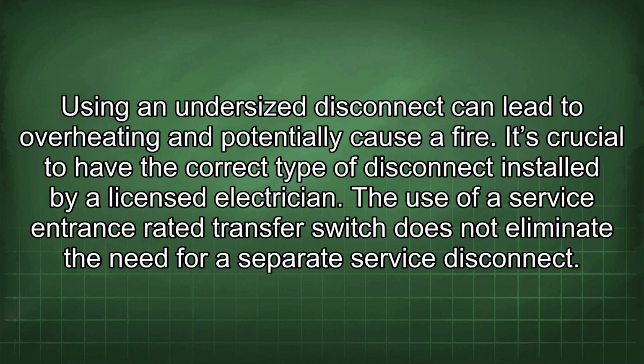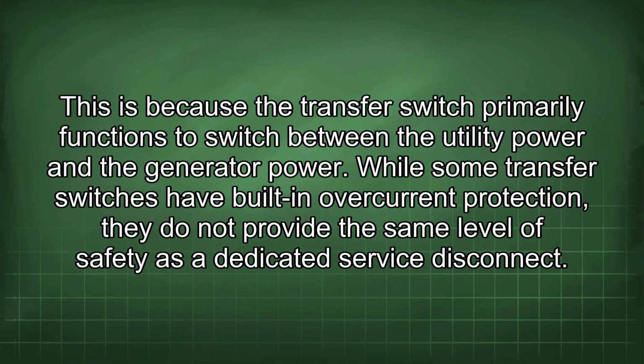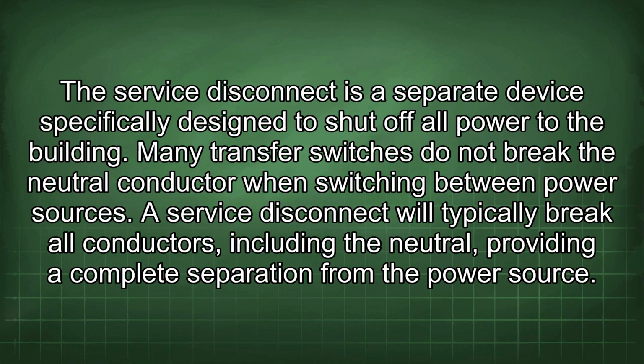The use of a service entrance rated transfer switch does not eliminate the need for a separate service disconnect. This is because the transfer switch primarily functions to switch between the utility power and the generator power. While some transfer switches have built-in overcurrent protection, they do not provide the same level of safety as a dedicated service disconnect. The service disconnect is a separate device specifically designed to shut off all power to the building. Many transfer switches do not break the neutral conductor when switching between power sources. A service disconnect will typically break all conductors, including the neutral, providing a complete separation from the power source.